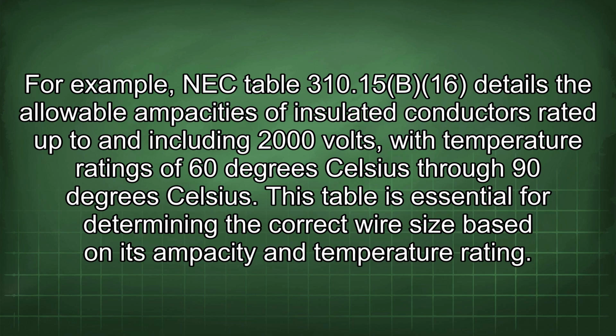310.15(B)(16) details the allowable ampacities of insulated conductors rated up to and including 2000 volts, with temperature ratings of 60 degrees Celsius through 90 degrees Celsius. This table is essential for determining the correct wire size based on its ampacity and temperature rating.